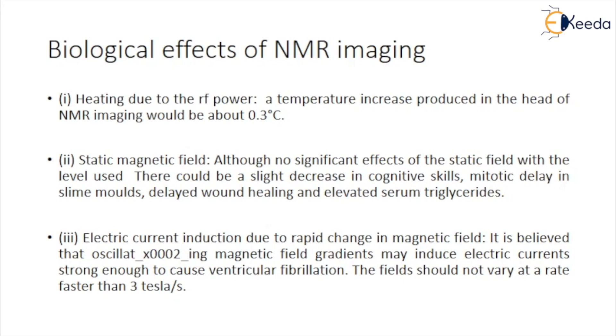Electric current induction due to rapid change in the magnetic field: it is believed that oscillating magnetic field gradients may induce electric currents strong enough to cause ventricular fibrillation. No damage due to NMR exposure has been reported, but it is still suggested that the field should not vary at a rate faster than 3 tesla per second.